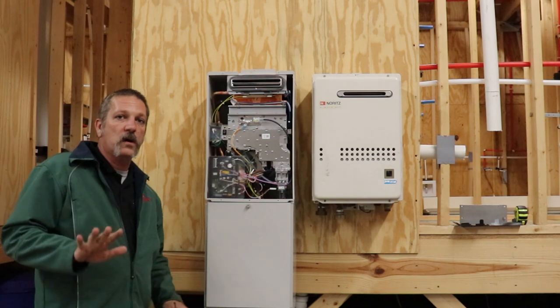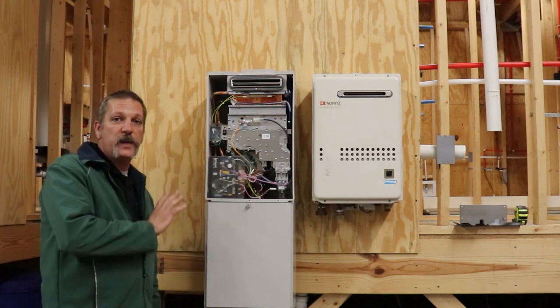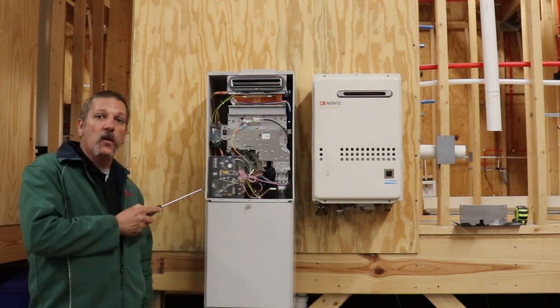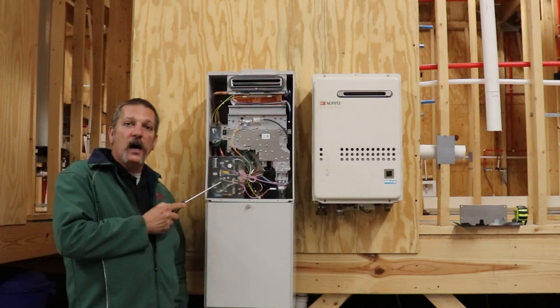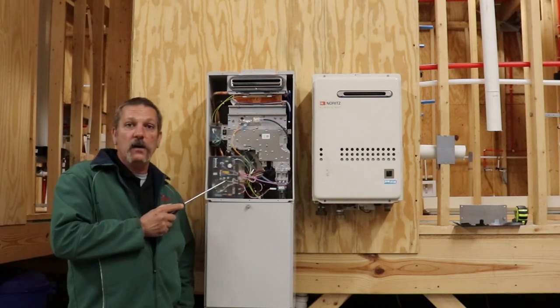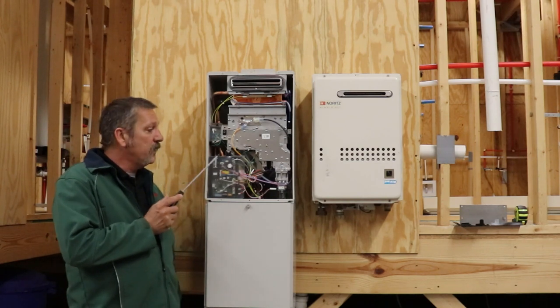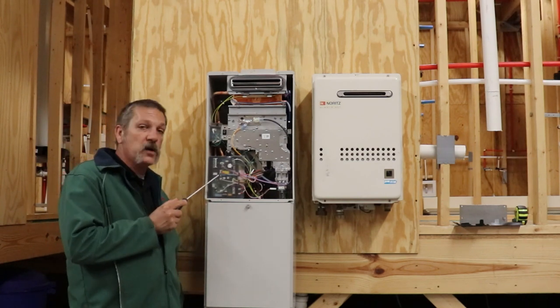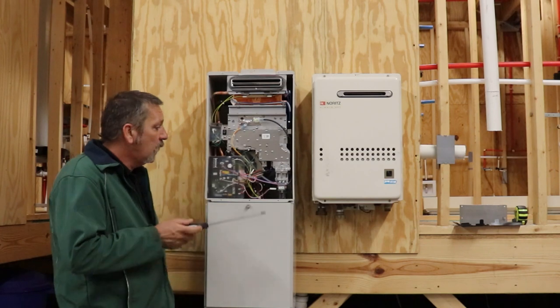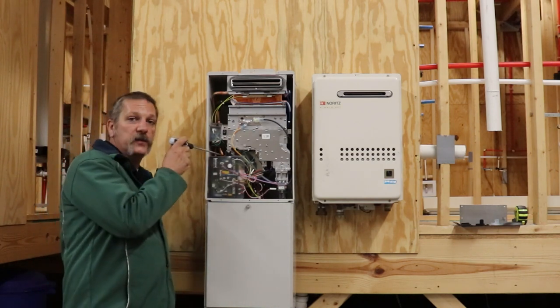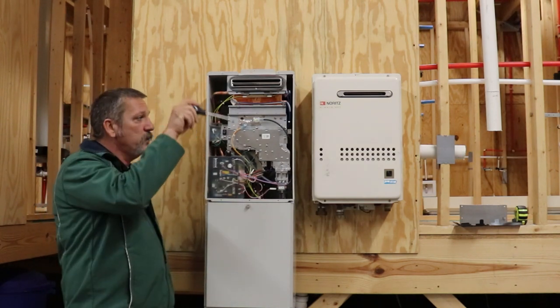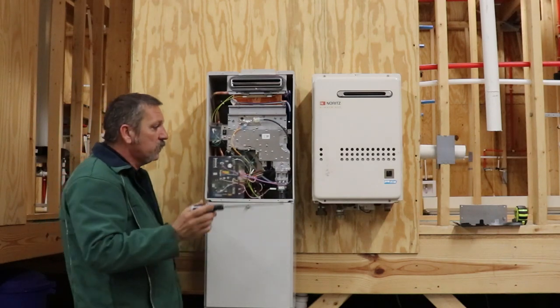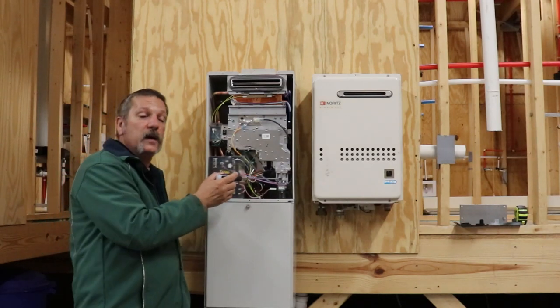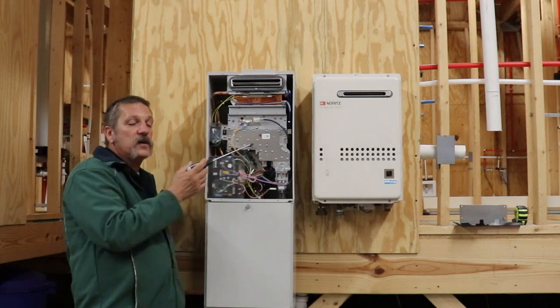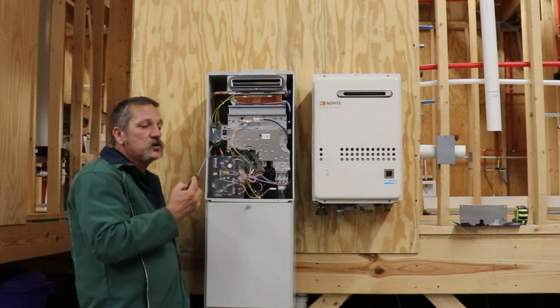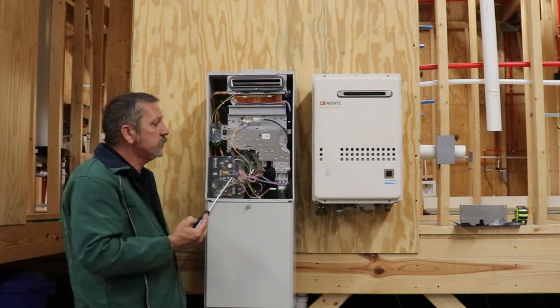Now, pretty much all tankless water heaters have these basic components. You're going to have your motherboard. That's the little computer brain right there that tells it when to turn on and when to do what it needs to do. They're all going to have some form of circuit board, some form of motherboard. The next thing is back behind here, there's a fan motor, which is blowing air up through this to push the exhaust out. You've got a gas valve that's going to open and close to let gas in. You've got your manifold here, and that's going to distribute that gas and regulate those pressures.